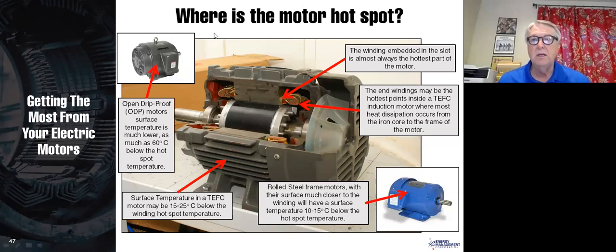Now, the question is, number one, where is the hot spot, and how hot can a motor be? If you have temperature measurements inside the motor, that of course is wonderful, but most people don't do that on these little small motors, just simply due to cost. So where is the hot spot, first of all? Well, we typically say that the hot spot is in the iron right here in the windings. And so we would put a temperature measurement device, if we were going to put one in the motor, in that location. Now, it is possible that sometimes the hot spot is out here on the end turns. And so right there's your end turns. So that's possible, but typically we put it in here.